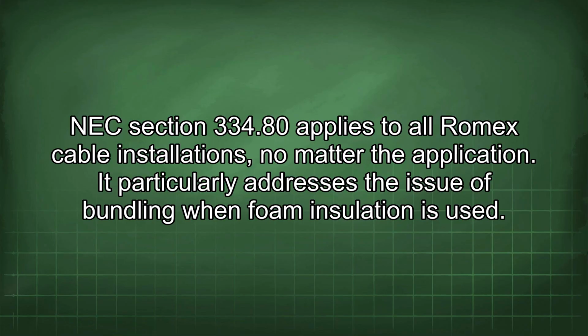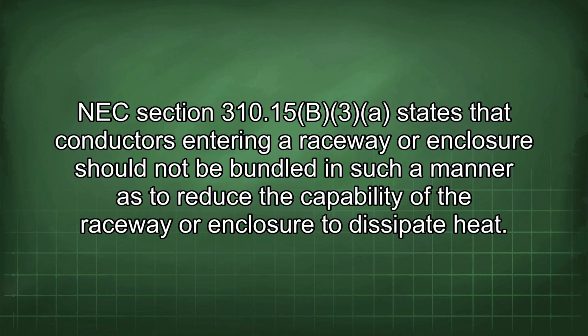NEC Section 334.80 applies to all Romex cable installations, no matter the application. It particularly addresses the issue of bundling when foam insulation is used. NEC Section 310.15(B)(3) states that conductors entering a raceway or enclosure should not be bundled in such a manner as to reduce the capability of the raceway or enclosure to dissipate heat.